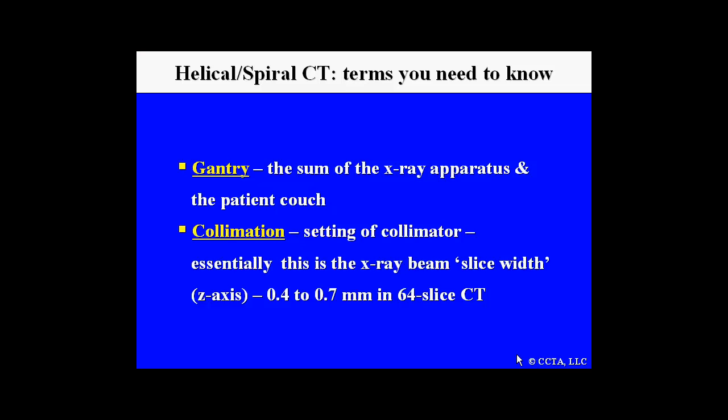Terms that you need to know involve the gantry, which is the sum of the x-ray apparatus and patient couch. Collimation, which is really the post-patient collimator, is basically the setting of the slice thickness. Slice thickness in traditional 64-slice scanning varies between 0.4 to 0.7 millimeters.